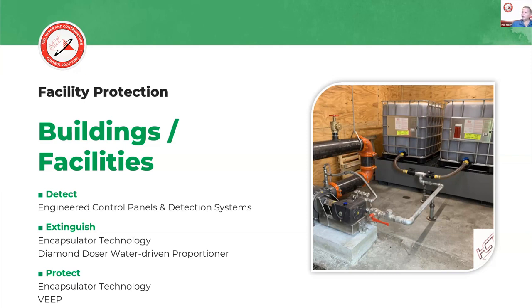What you're seeing here in the picture on the right is what we call our diamond doser. It's a water-driven proportioner. We've got totes of F500 on a catchment basin that feeds into the diamond doser. It's water-driven, no power required other than water movement. As water moves through the sprinkler riser, it powers this water motor and proportions agent into the system appropriately for the hazard being protected.